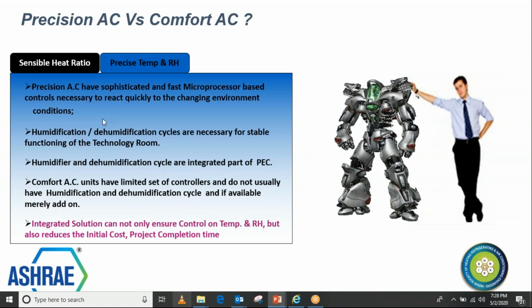Imagine that your humidity is high in any application. Let's take the example of a computer room or a server room. In a server room, if your humidity is high, what happens there? You will end up having condensation issues. The same issue will happen whether it's a VFD room or a control room. Having more humidity, you will end up having condensation there.